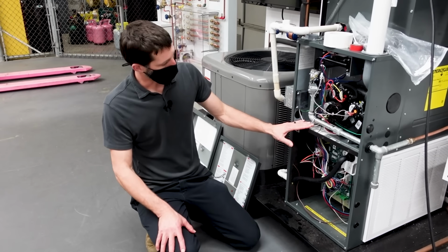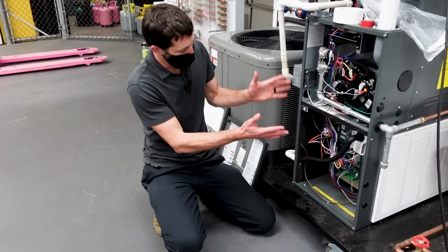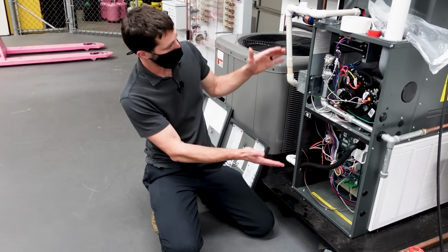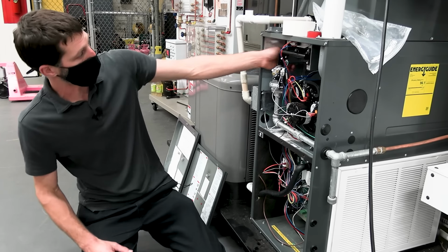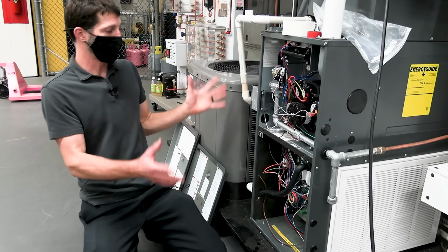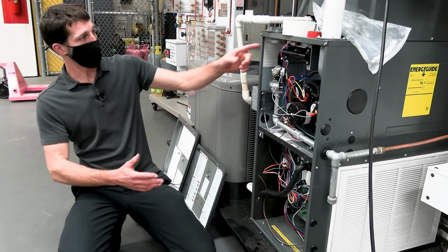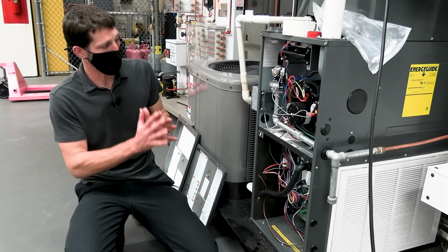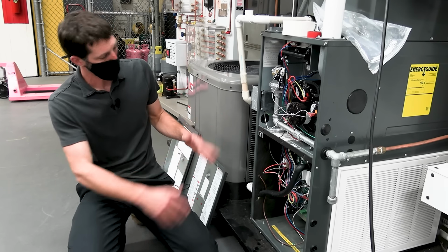What happens first is you're on a call for heat. What's going to already happen is the control board is already monitoring all the safeties, and if any of those safeties are open, such as the thermal limits, then it's going to either run the fan, or depending on if it's a cracked heat exchanger, it may run the inducer motor, but usually it's running the fan. And it may have an error code.